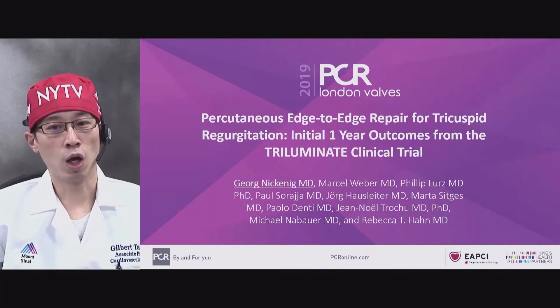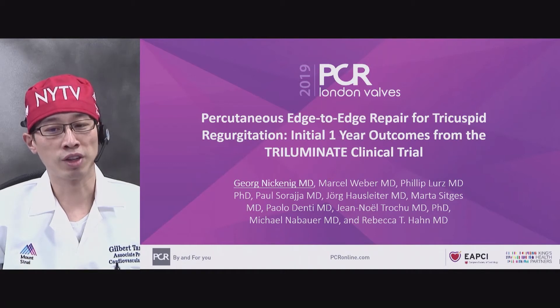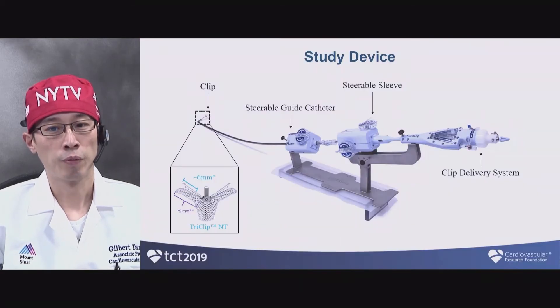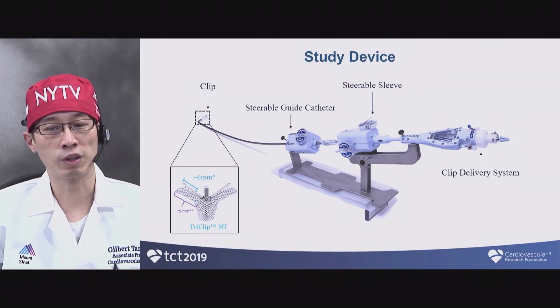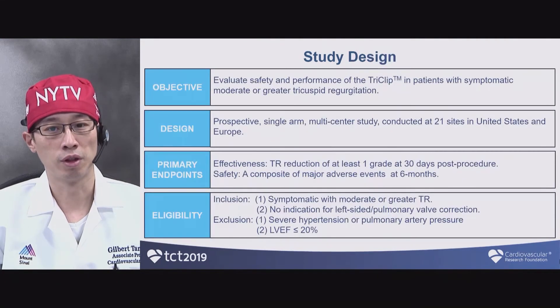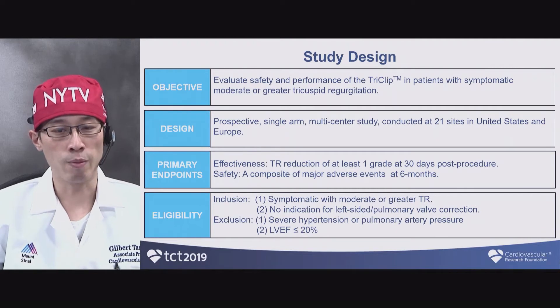These are the latest results of the Triluminate study, which is the early feasibility multicenter global study — one-year results just presented at London Valve. I am one of the investigators for this study. The TriClip device used here has shorter clip arms but is dedicated for the tricuspid position. The study design involved 21 sites in the U.S. and Europe, with the goal of reducing TR grade by one at 30 days post-procedure.